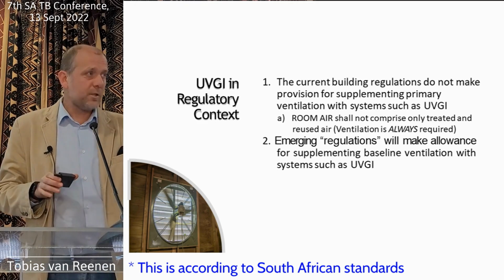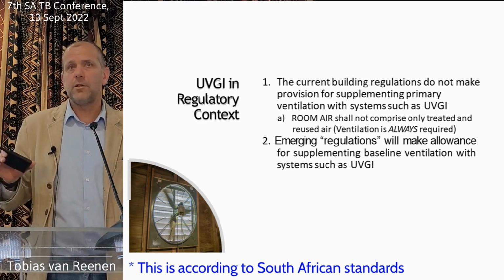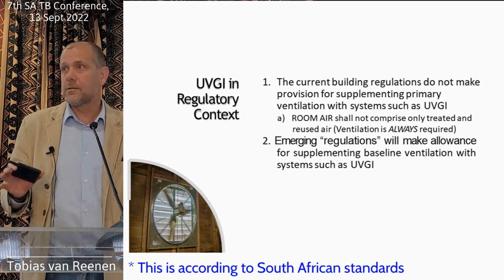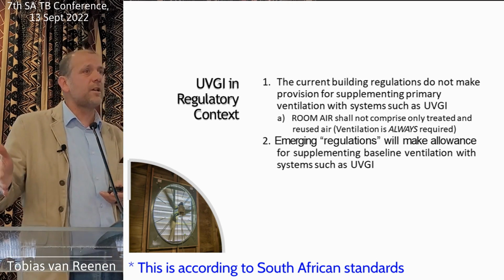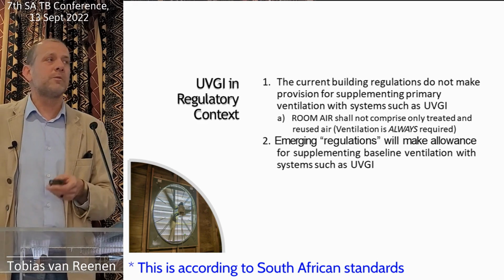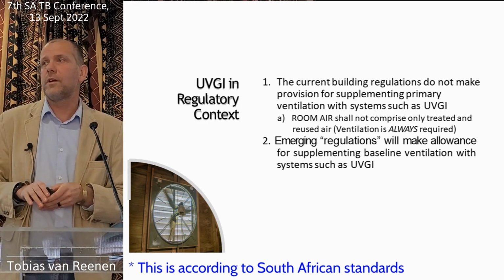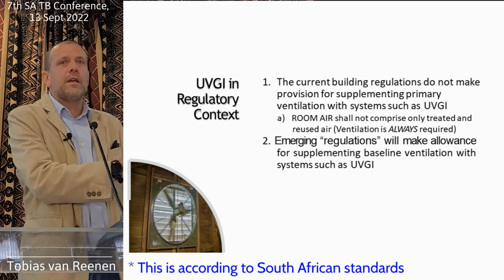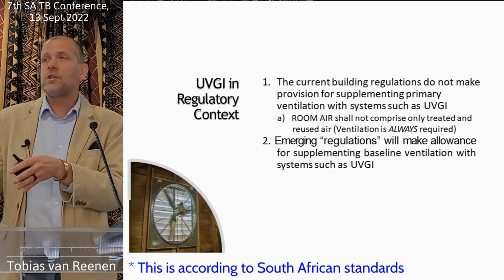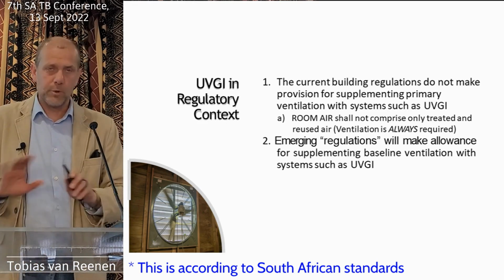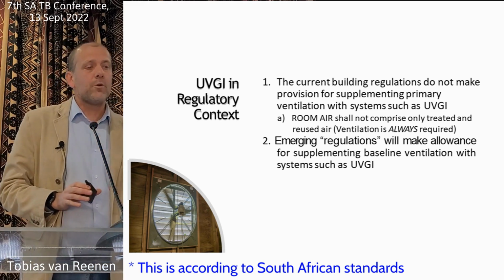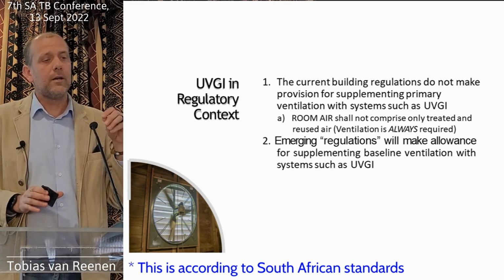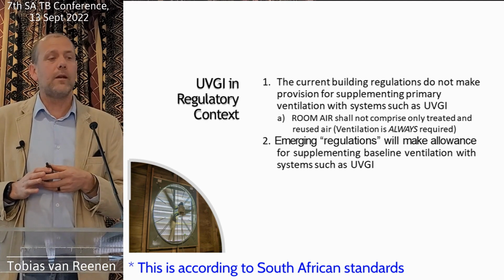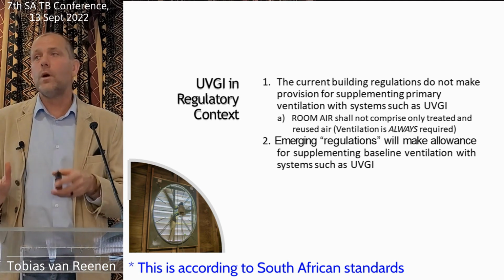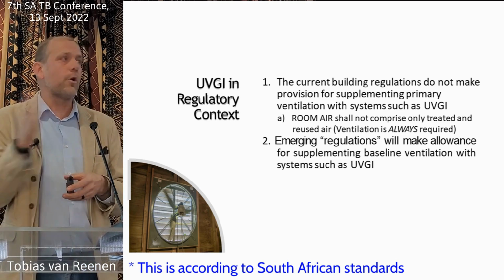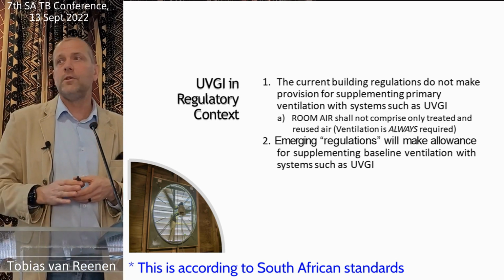So where it says you must do 6 air changes or 10 air changes or 12 air changes, that's it. You've got to provide that ventilation rate. No supplementary systems may be considered to be part of that 12 air changes. So you can't do 6 air changes mechanically ventilated and 12 air changes with a UVGI system. Not allowed. And that room air shall not comprise only treated and reused air. So ventilation is always required. You can't throw away your ventilation and replace it with UVGI.